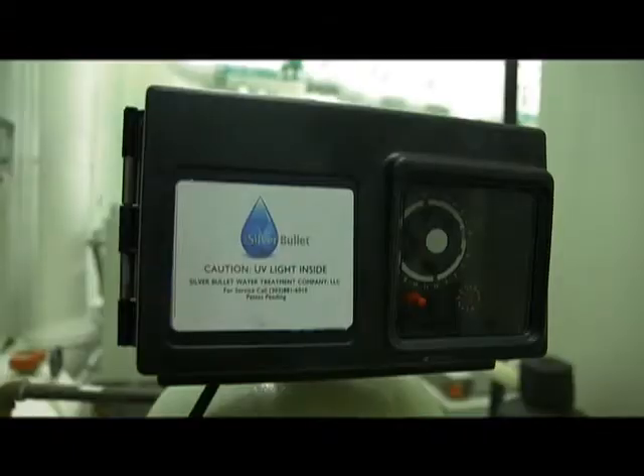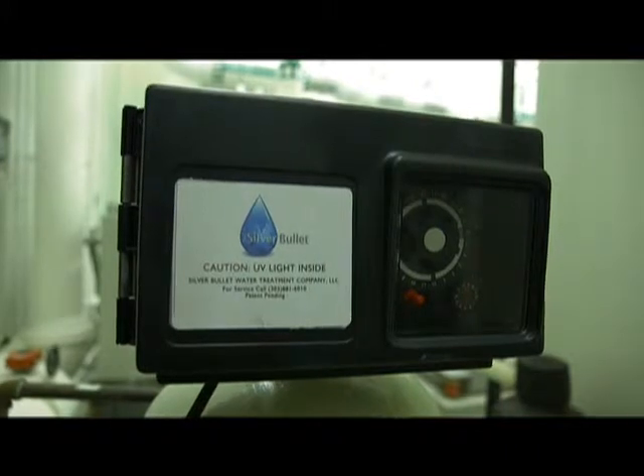I was sold by the fact of the Silver Bullet, just in the performance and reducing scale. The percentage of scale that you reduce certainly has a dramatic impact on energy savings, electrical savings. We're saving money by improving the heat transfer, by removing scale from the systems, and also increasing the cycles of concentration within the condenser water. So that's also allowing us to save water. We use less water, I think we've increased to 6, sometimes 7 cycles of concentration.